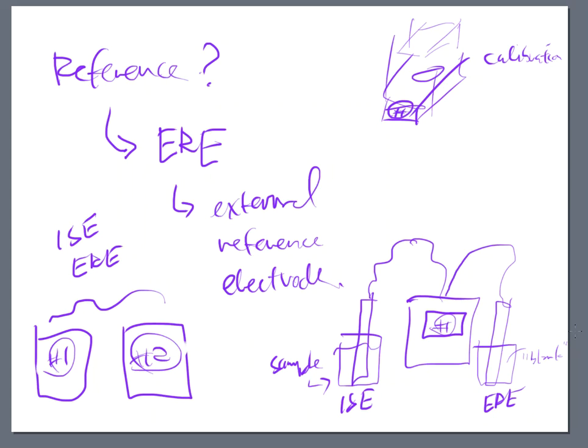Well, that means that every single time I had to do a measurement with the pH meter, I had to make sure that this probe was cleaned and taken care of and placed into this reference solution. And I had to make sure that this probe was also clean and taken care of and placed into my sample solution. And now I'm worrying about two probes, right? And what if I damage one but not the other? Things still had to be replaced. My meters weren't working the right way. This was a mess. But for the longest time, pH probes were built this way. They were two component probes.